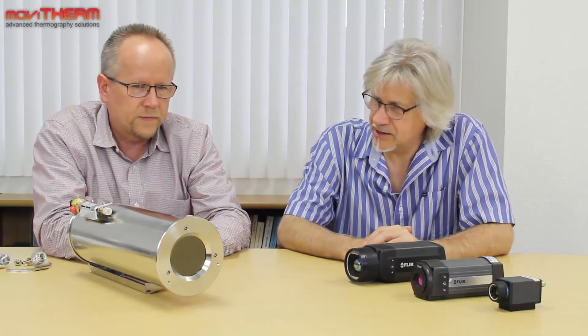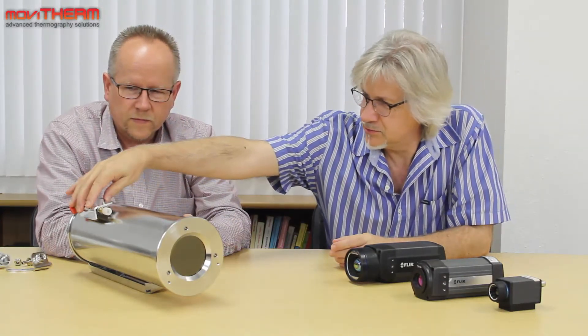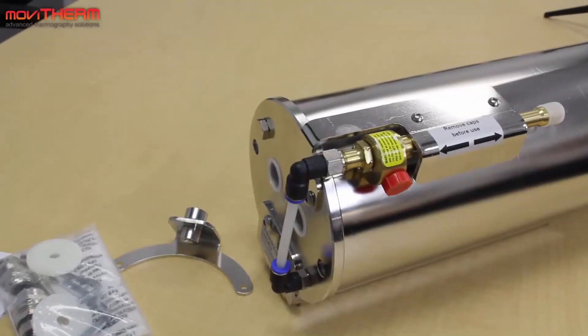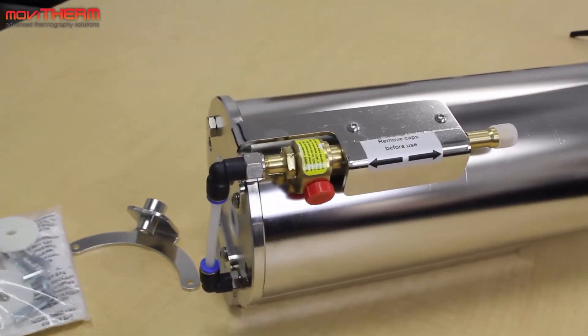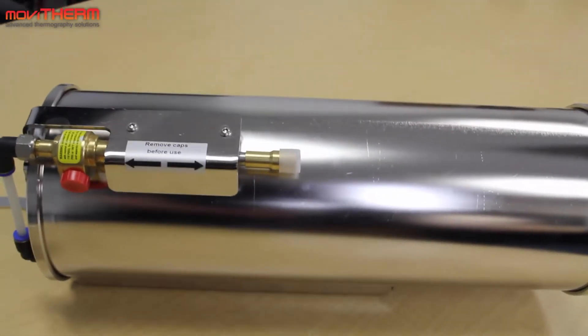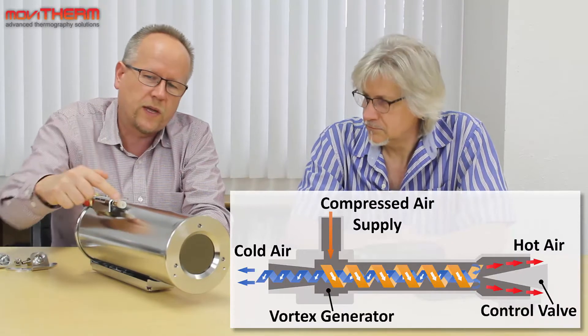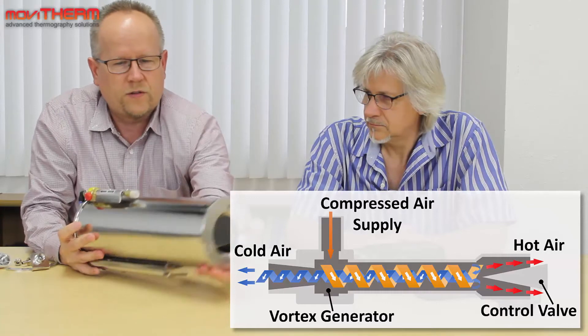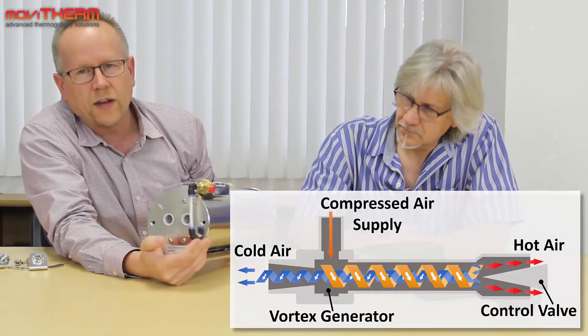This enclosure comes with a special cooling option, this is actually a vortex tube and that allows us to connect compressed air here and it actually separates the compressed air into a hot air stream that comes out the top up front here and a cold air stream that goes into the back of the enclosure here.